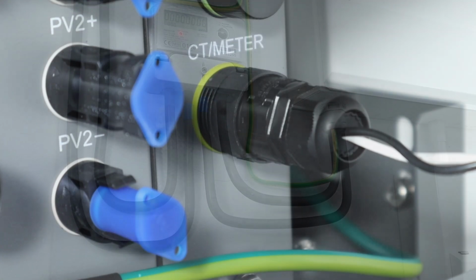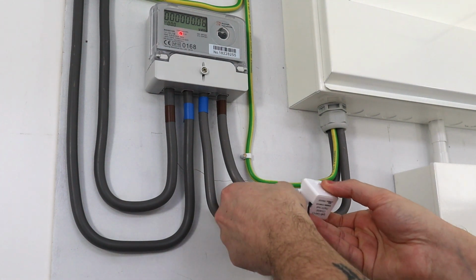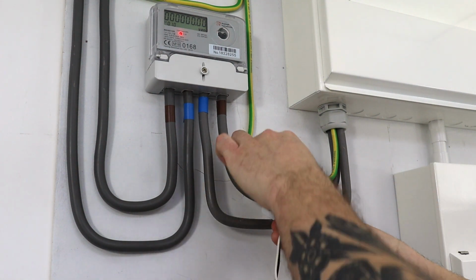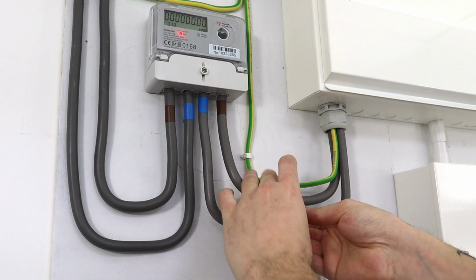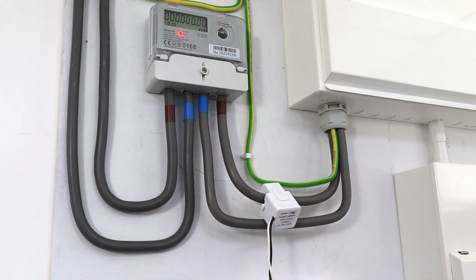At the other end, clip the CT over the live mains incomer. This method of connection is effective for distances of up to 50 meters between the inverter and mains in, and uses the inverter to calculate the house load to enable discharge from the battery. Ensure the arrow on the CT is pointing in the correct direction. When placed between the consumer unit and the mains incoming meter, the arrow should point towards the meter.